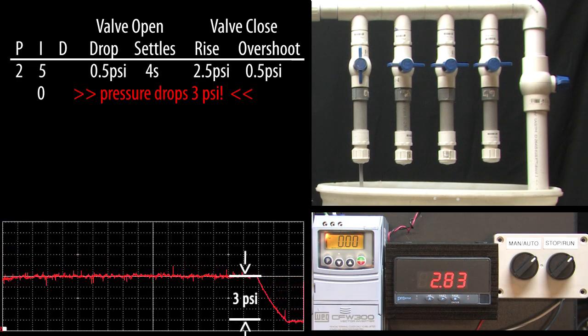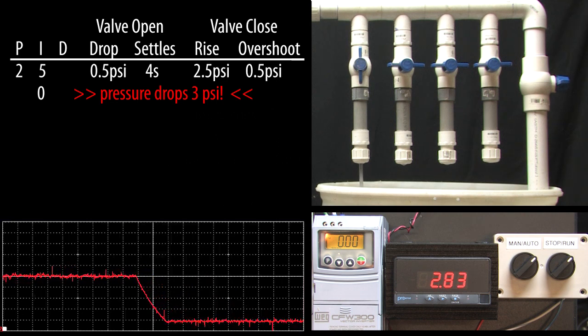And that's a key point to understand about PID. The P term by itself can never get you all the way to your target because once the error gets really small, the P term becomes too small to affect change in the motor speed. Some systems P only will get you really close, but in pumping systems like this one the effect is really pronounced. The way we get around that is by adding the I term.